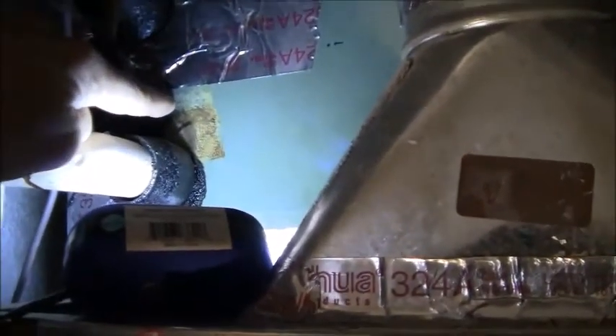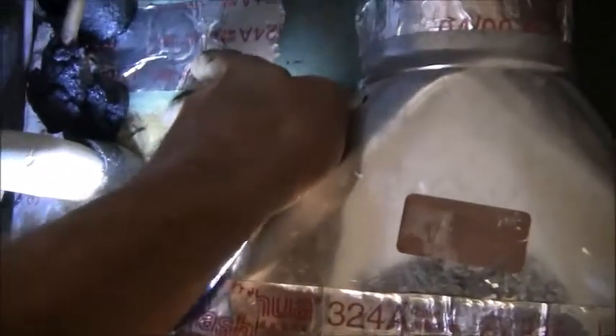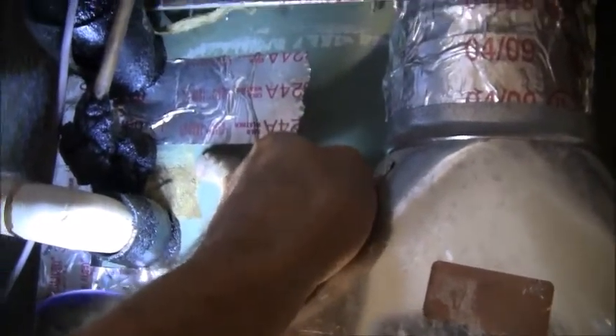Now, before I drilled that hole, I first looked at the unit. If you look at the way the unit is constructed, you can see the liquid line is here. Let me get a flashlight so you can see this a little bit better. Okay, this is the liquid line. My finger is touching the liquid line. This is liquid refrigerant coming in. It's supposed to be going to an expansion valve, some type of metering device inside of this unit.